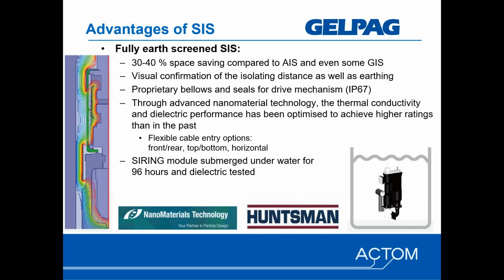It incorporates proprietary bellows and seals, which are critical to ensure the isolation for the drive mechanism to the moving parts within the embedded pole, the screened embedded pole. And through advanced nanomaterial technology, the thermal conductivity and dielectric performance have been optimized to achieve higher ratings than have been achieved in the past. We'll look at those as well during this webinar.